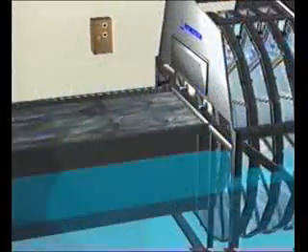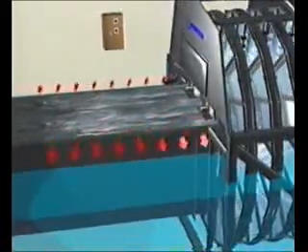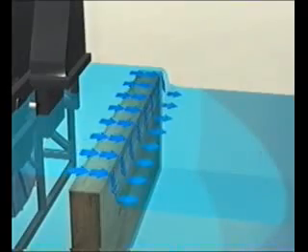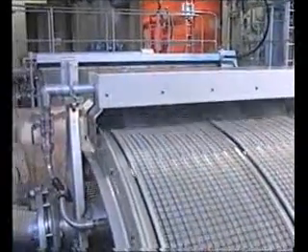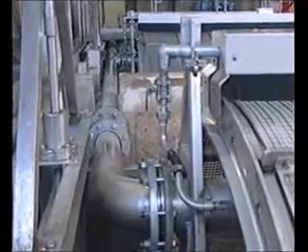Should the flow capacity through the filter cloth be reduced for any reason, for example due to increased sludge content in the water or backwash failure due to the pumps breaking down, the water must be led past the filter via an inbuilt or external bypass system. The separated particles are backwashed into the sludge trough and piped away for treatment, whilst the filtered water continues on through the process.